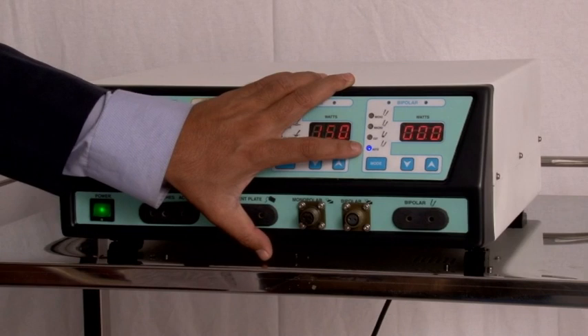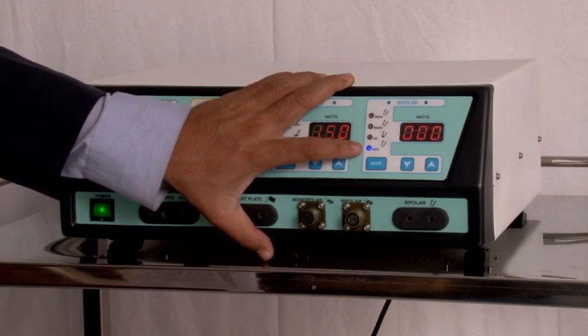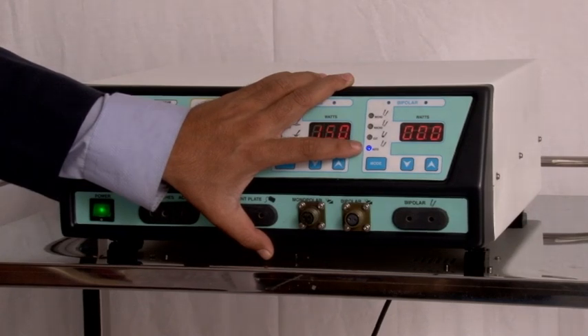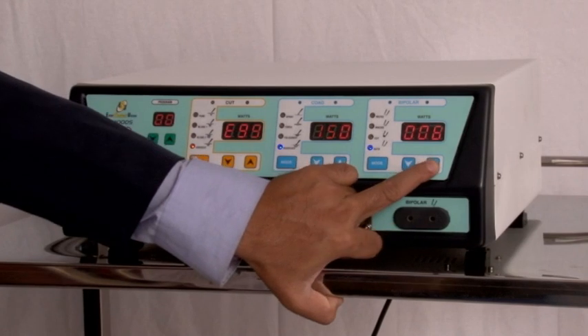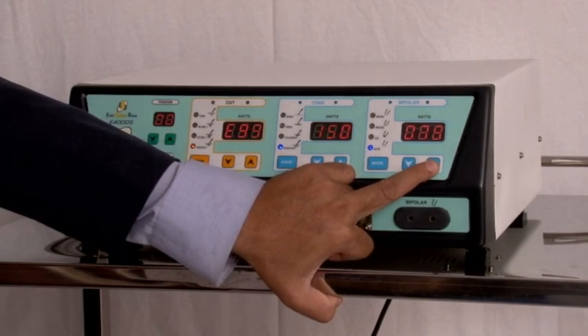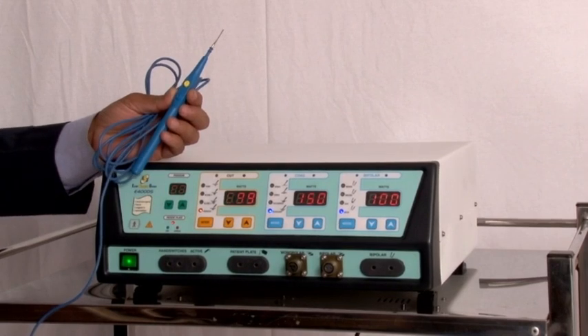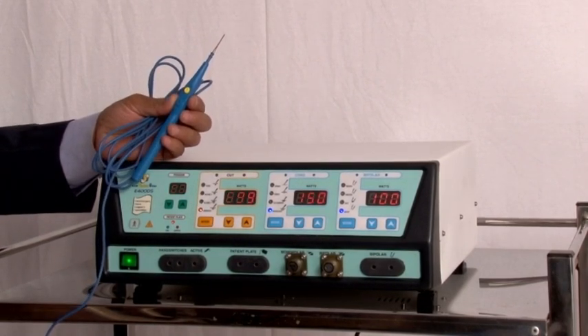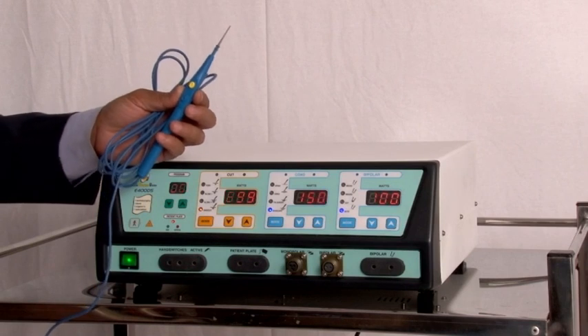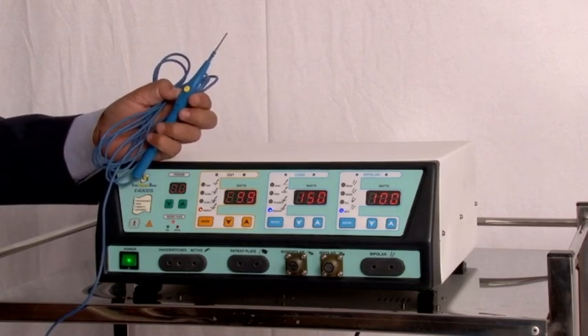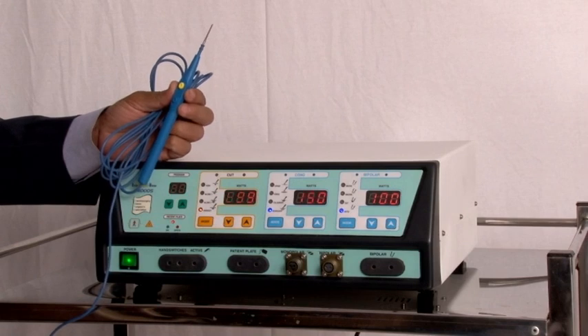Last mode in bipolar is auto mode. Automatic stoppage of bipolar output and an audio sound once the coagulation is achieved is a specialty of auto bipolar mode. This mode assures coagulation without damaging peripheral tissues. Auto bipolar has a maximum output of 100 watts. Electrosurgical generator E400DS is supplied with many standard accessories. First one is a disposable monopolar hand switch.